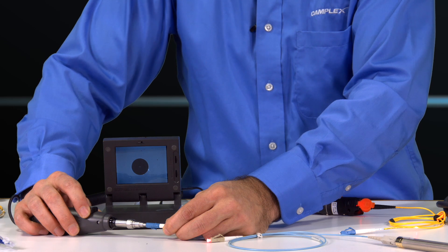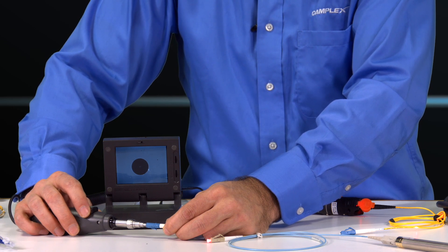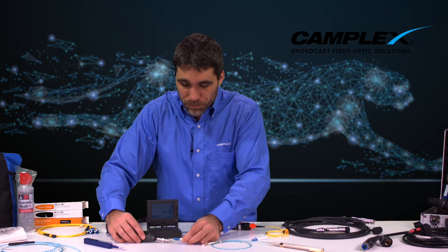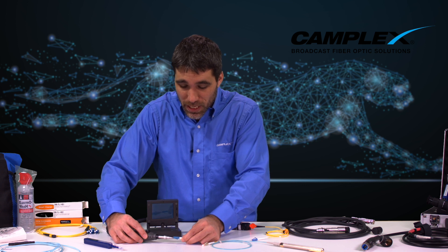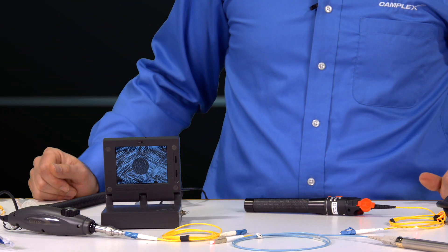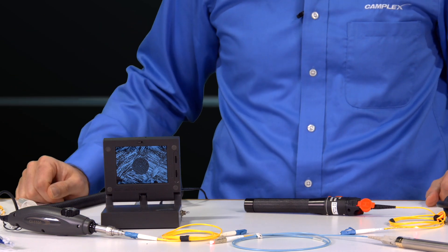I do have a little chip on the end of this cable. It is outside the end face of the cable, so that's not too bad. But it's very important that you're cleaning and maintaining those fiber optic cables. If you're not, your cable may become the weakest link in your chain and your system may go down at a mission critical event merely because you didn't maintain a cable — simple as one, two clicks.